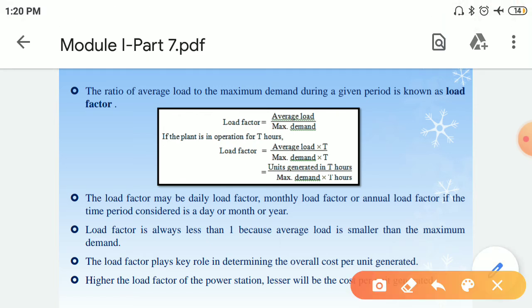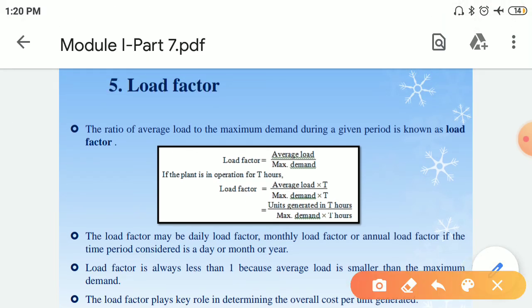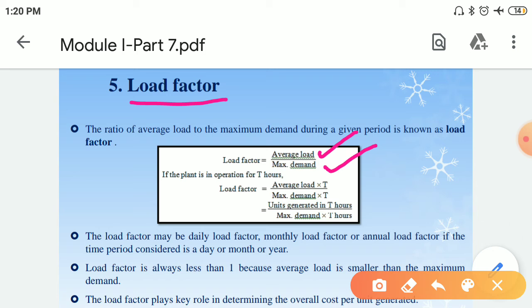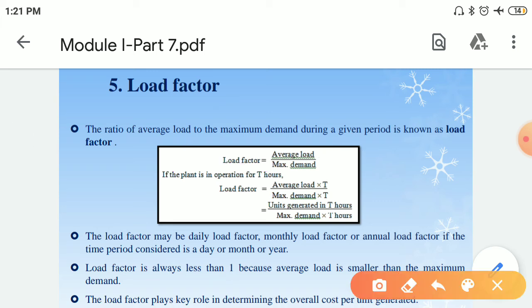The last term we are studying is load factor, which is an important factor. Load factor is the ratio of average load to maximum demand over a given period of time. We can find daily, monthly, or annual load factor depending on which load curve or time period is selected. The value will always be less than 1 because the maximum demand is always greater than the average load.